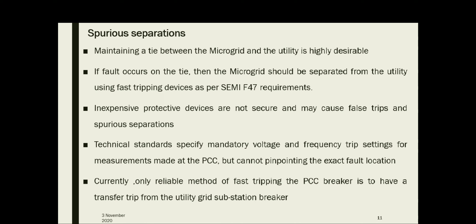Inexpensive protective devices are not secure and may cause false tripping and spurious separations. Fault tripping problems may arise not only from electromechanical release breakers, but also from sophisticated microprocessor-based protection packages acting solely on information available at PCC. If a microgrid supplies backup power to its own loads, then spurious separation can be tolerated to a certain extent.